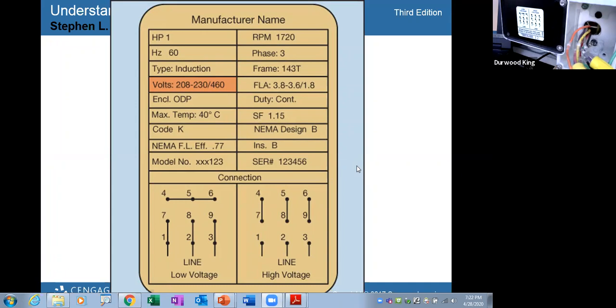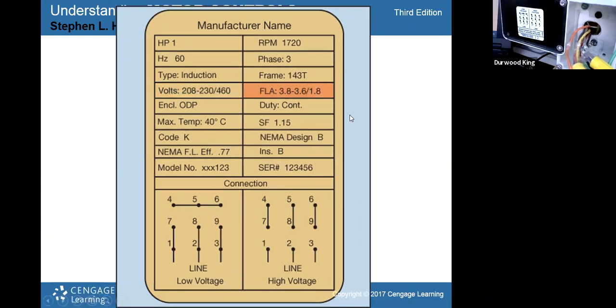Okay, so that was your dual voltage. And then FLA is full load amps. The full load amps is what you can expect if the motor actually has a load on it, driving a gearbox or a pump. It would draw in the range of 3.8 amps to 3.6 amps. When you're wired at 208, the motor would draw 3.8 amps. If you're wired at 230, when you increase the voltage to the motor, the amp requirement goes down to 3.6.